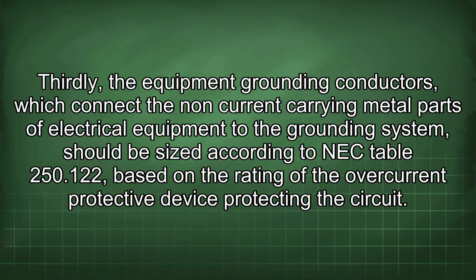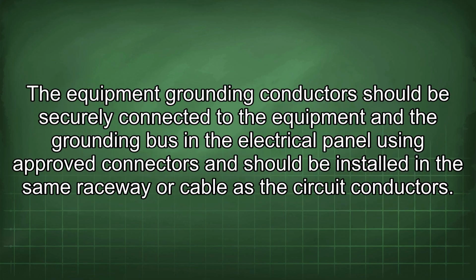Thirdly, the equipment grounding conductors, which connect the non-current carrying metal parts of electrical equipment to the grounding system, should be sized according to NEC table 250.122, based on the rating of the overcurrent protective device protecting the circuit. The equipment grounding conductors should be securely connected to the equipment and the grounding bus in the electrical panel using approved connectors and should be installed in the same raceway or cable as the circuit conductors.